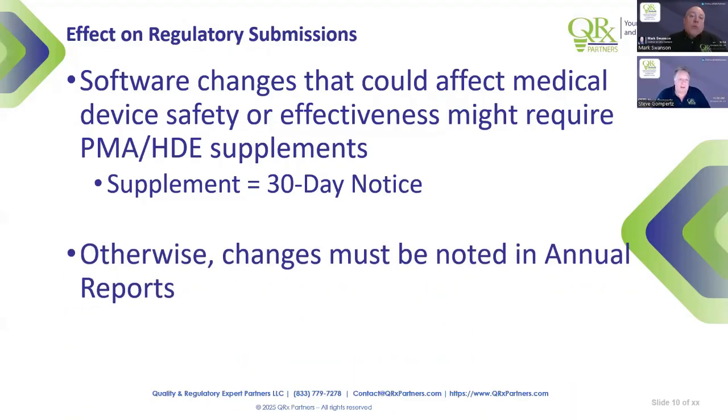Even if you say, look, it can't, right? If you're building a device that's on a PMA or an HDE, you are creating annual reports, you would still capture it as part of those annual reports, right? So you don't need to do a 30-day notice, but you still need to make note of the fact that you made these changes, and here's how you know that that was okay. So again, the key is they're reminding you, right? There's a connection here to the submissions that you've done.